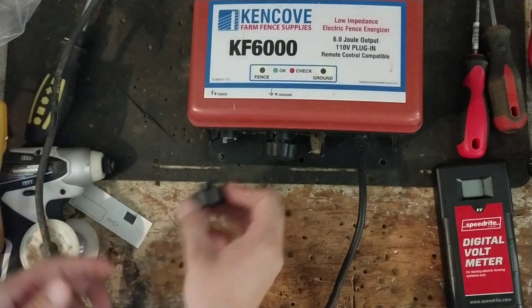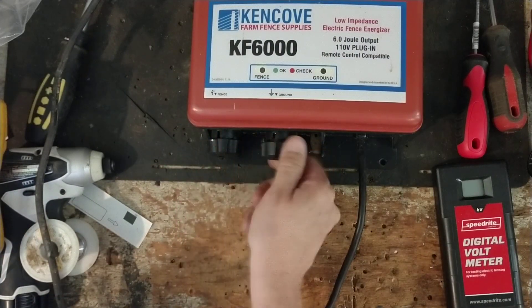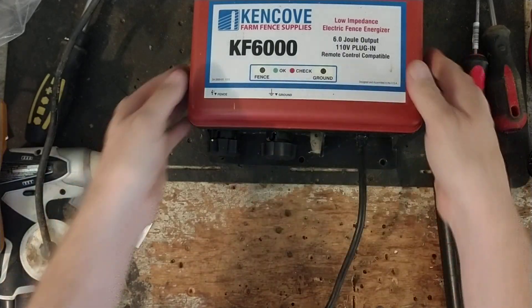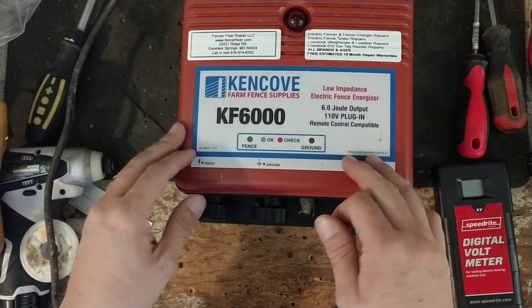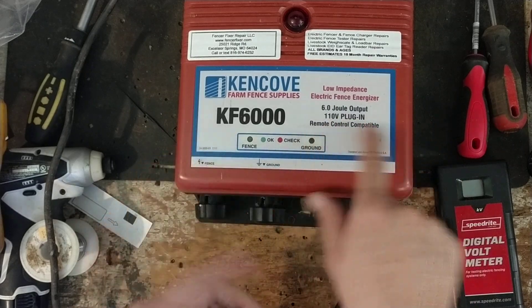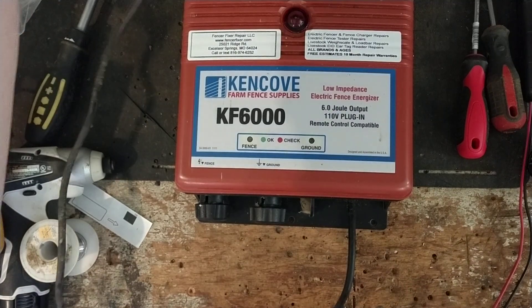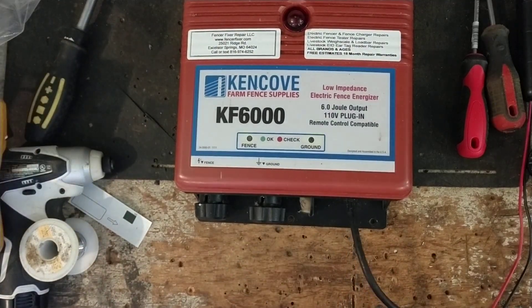These Kencove slash Power Wizard units — or Dare units — aren't a bad unit. Especially for the money that you pay for one of these, you're getting a pretty good shock for the money. You can also use a remote control, and it's low impedance. So that's another benefit of these things versus some of the old solid-state stuff.